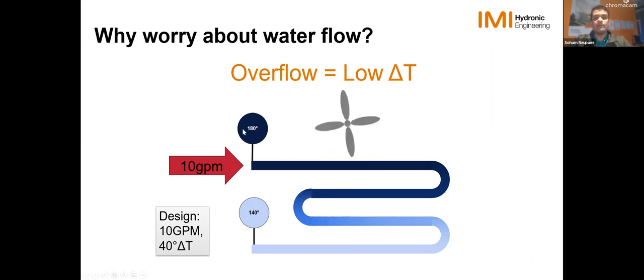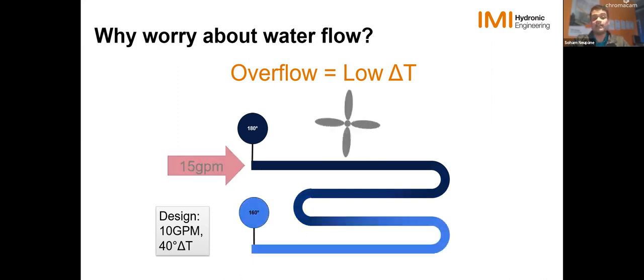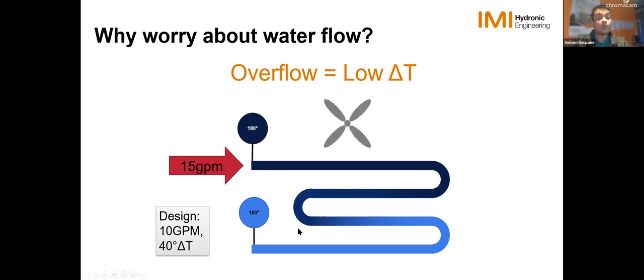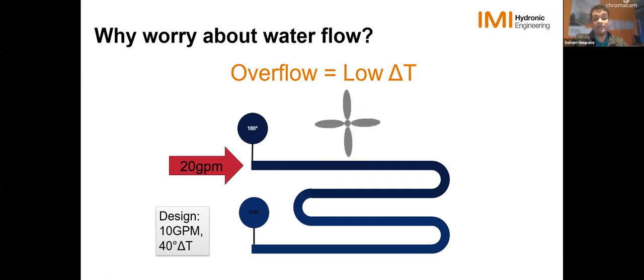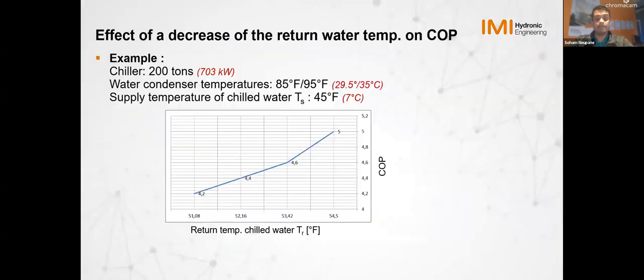So just for an example, say you have a heat exchanger with 10 GPM design flow and a 40-degree delta T. What happens when we start overflowing? Say instead of 10, now we're overflowing it by 50% and you got 15 GPM going in. And the delta T is now reduced to 20 degrees. And say the circuit is overflowing even further because we didn't have a proper balancing solution installed. What's going to happen to the delta T now? It's down to 10 degrees. So from 40 that we were originally looking at, you see this big impact on the delta T, and thus it's going to affect the performance of your chiller and boiler and all that.